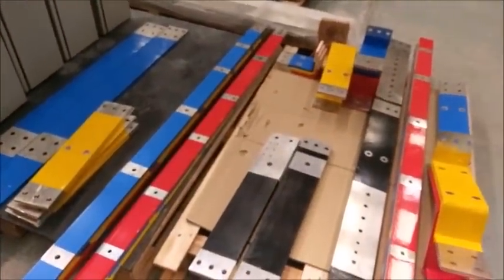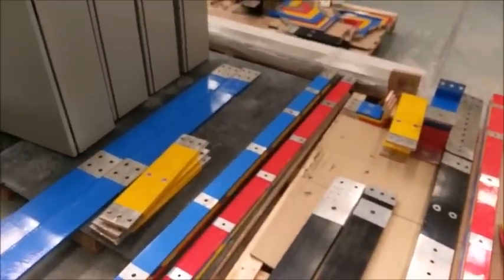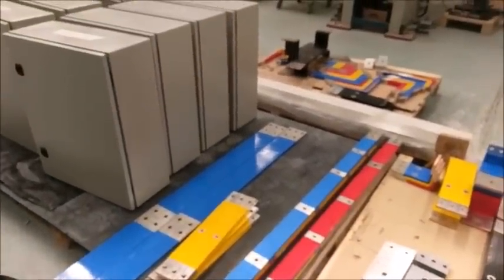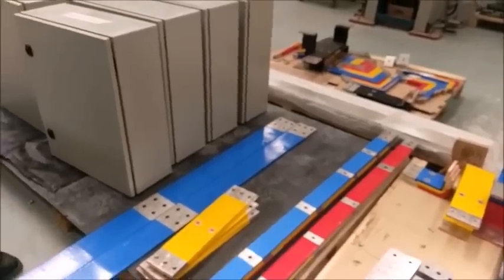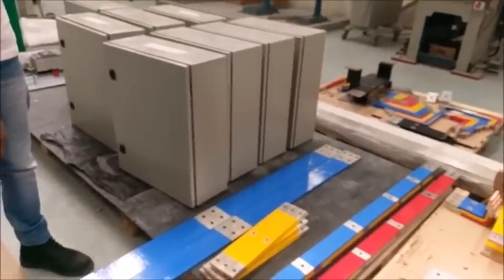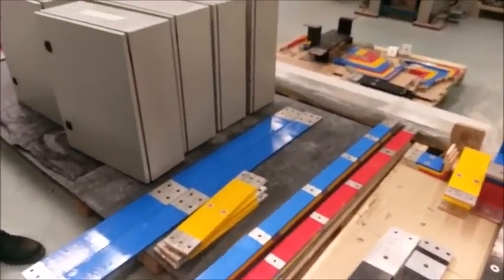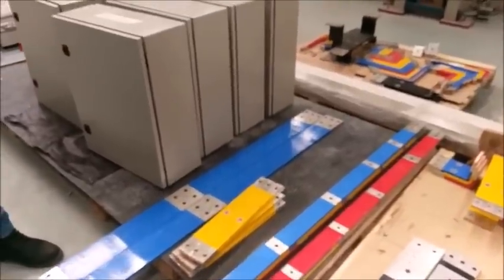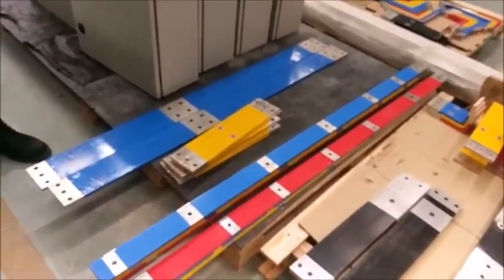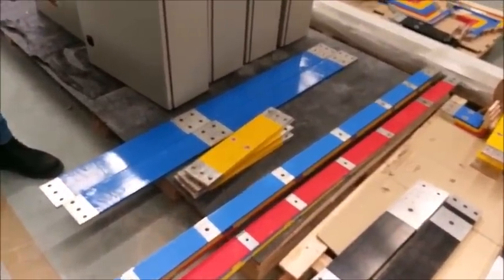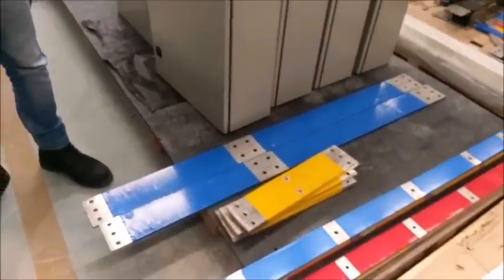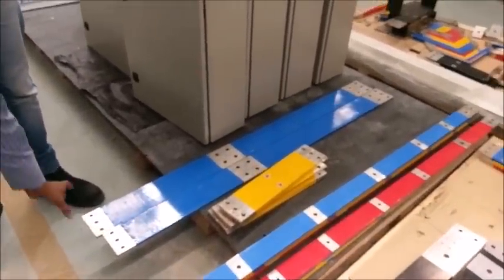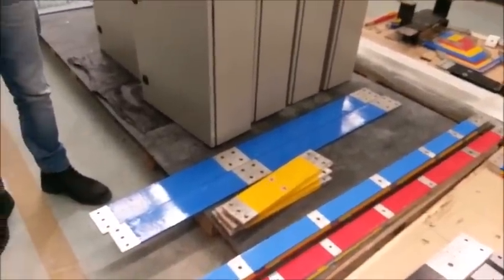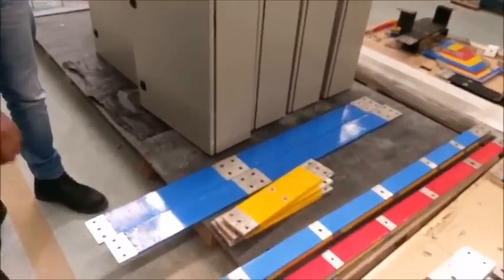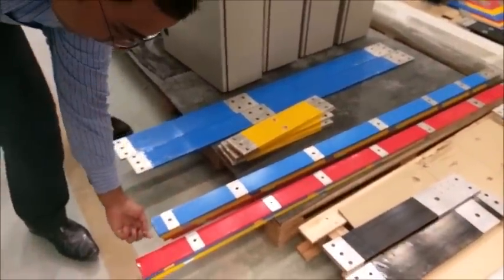Black is neutral. And the earth will be without any coding, as per regulation, without any color. Only an earthing tag will be there. What is the bus bar size? This is 100 by 10, width 100 mm and thickness is 10 mm. This is 60 by 10, 60 mm width and thickness is 10.